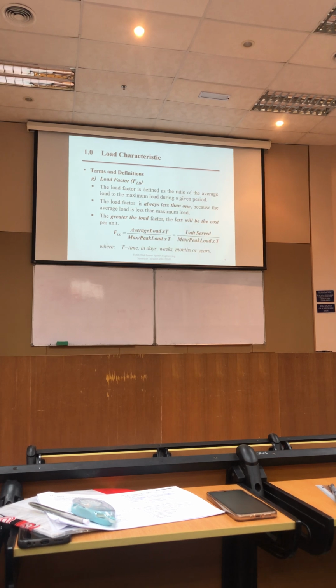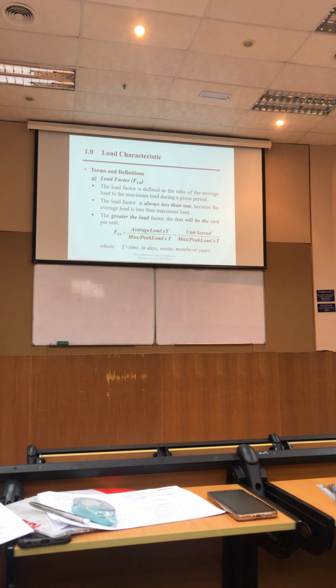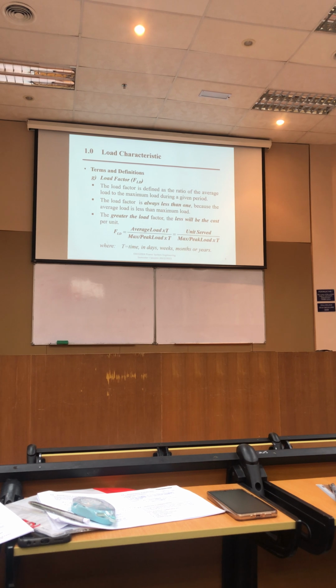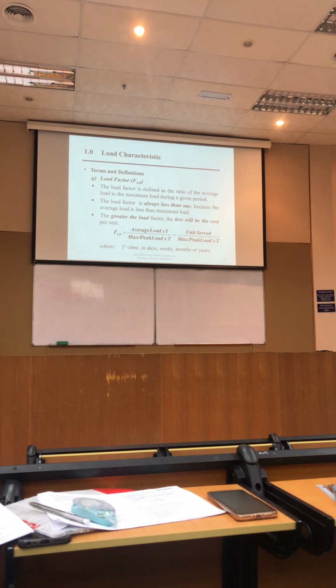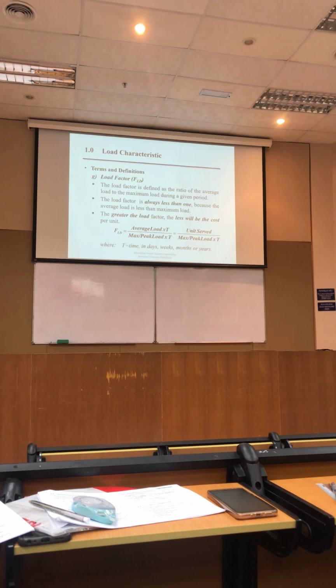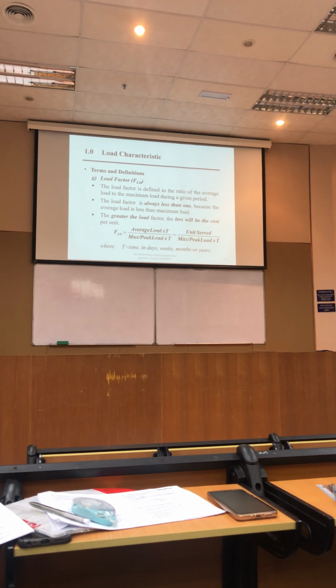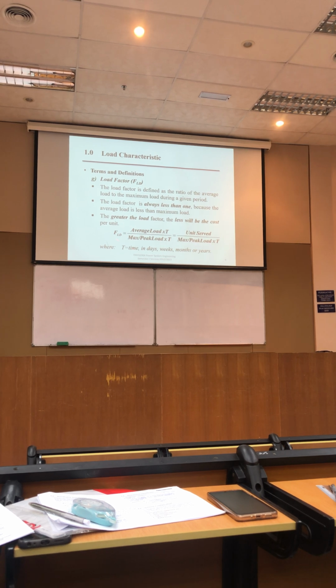Load factor, FLD. Ratio, nisbah, of the average load to the maximum load during a given period. The load factor is always less than 1 because the average load is always less than the maximum load. So the greater the load factor, the less will be the cost per unit. FLD equals average load times T, which is the units served, divided by maximum peak load times T. T in time will be in days, weeks, months or years.